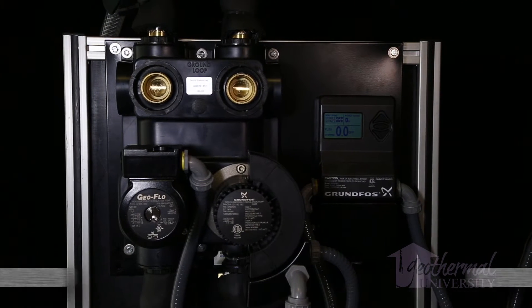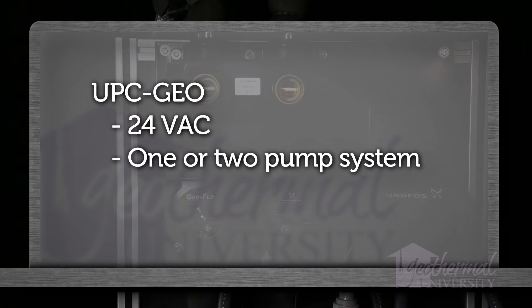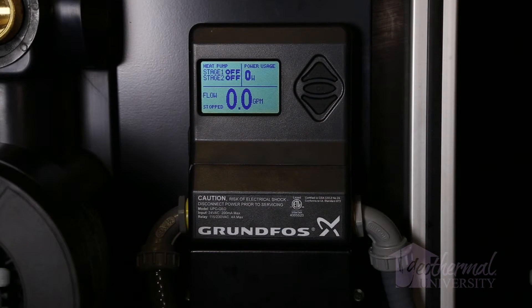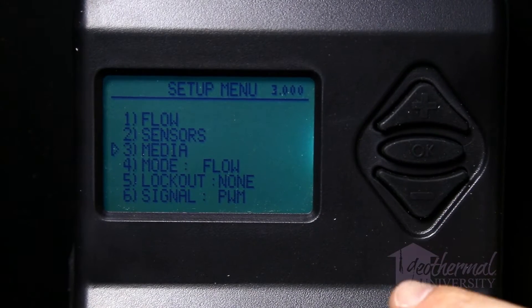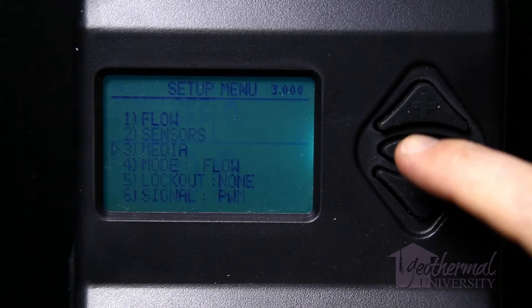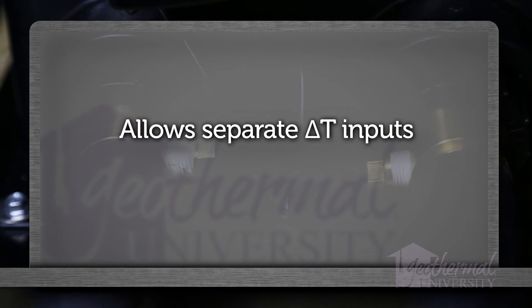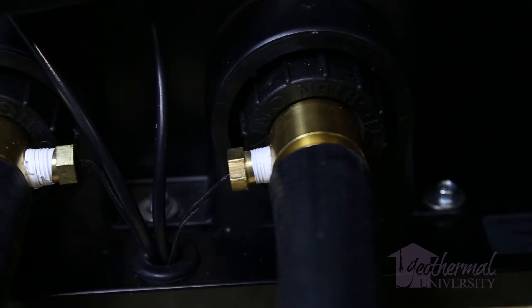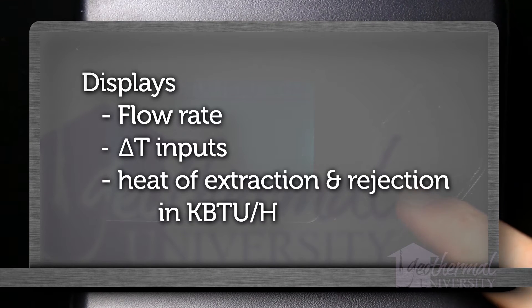Here's a quick overview of the variable speed flow center features. The Geo-Flo Universal Pump Controller UPC-Geo is a 24-volt AC powered control that operates one or two pump variable speed flow center systems to provide accurate pump control and feedback, resulting in the lowest possible power consumption. Installing a single Grundfos Vortex flow sensor or VFS with the UPC-Geo allows the system to be controlled using a flow rate set point input based on the requirements of the heat pump. Differential temperature control requires the addition of two immersion thermistors and allows separate delta T inputs for heating and cooling modes. Installing both the VFS sensor and thermistors allows the UPC-Geo to display flow rate, delta T, and heat of extraction and rejection in thousands of BTUs per hour.